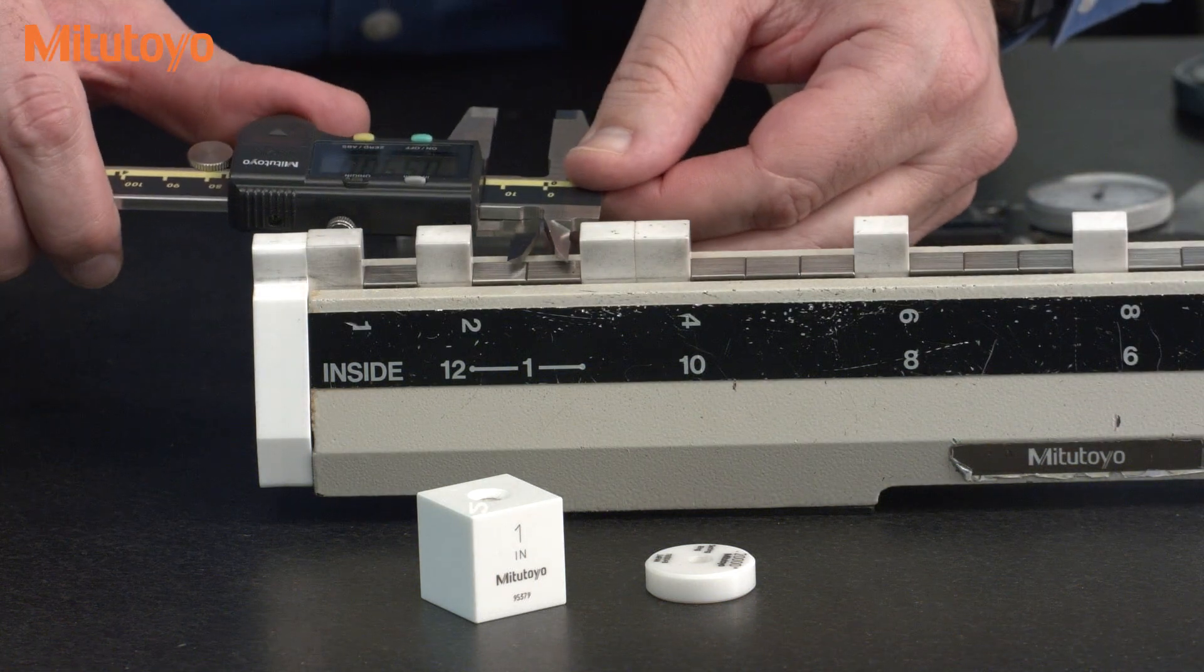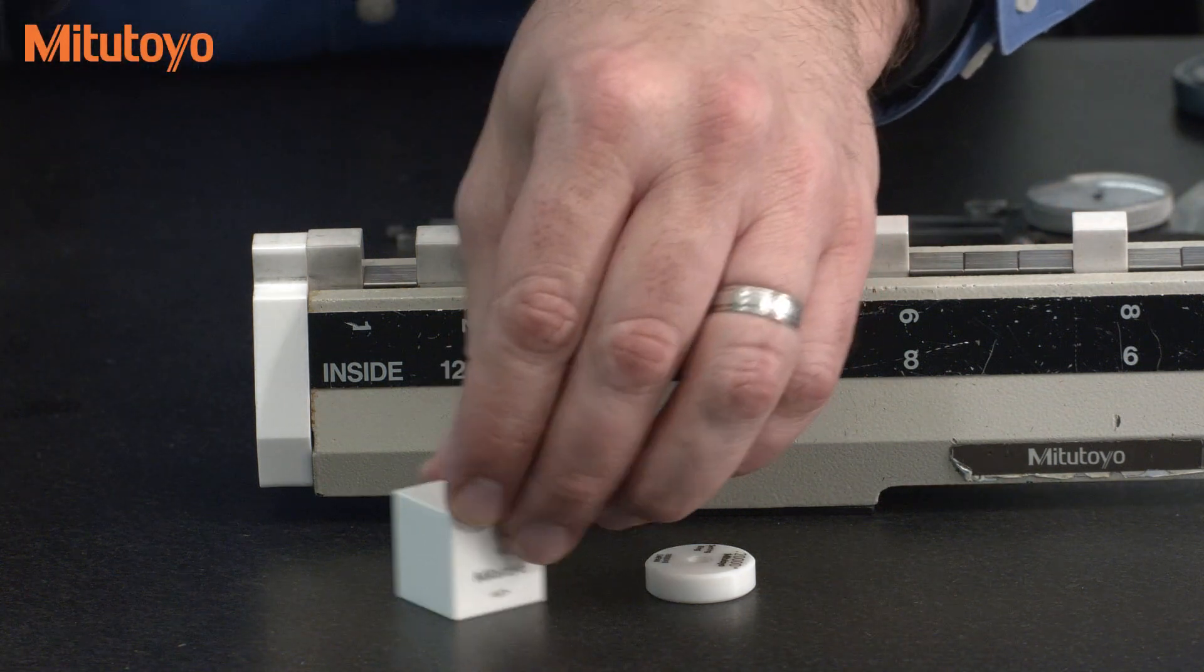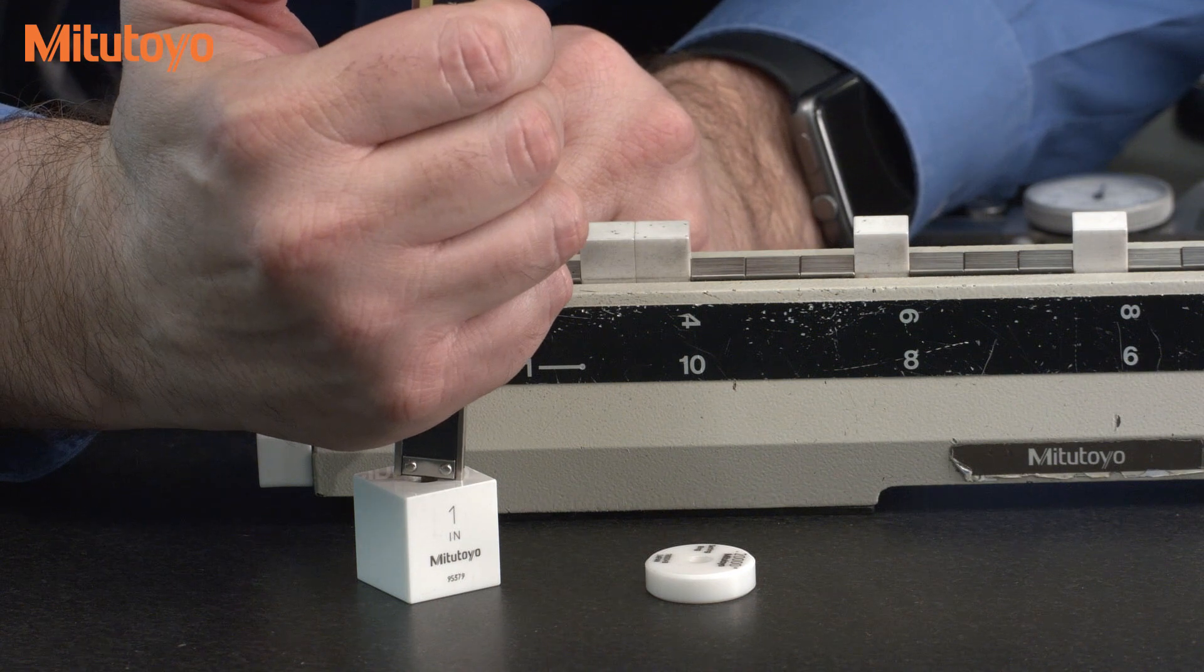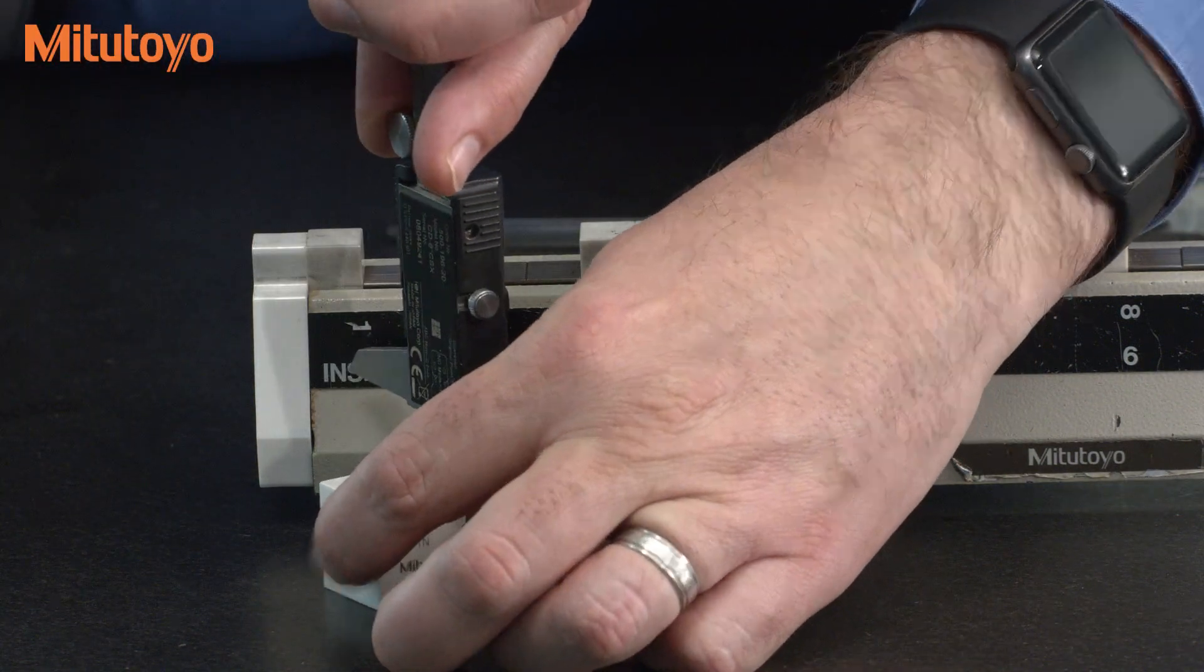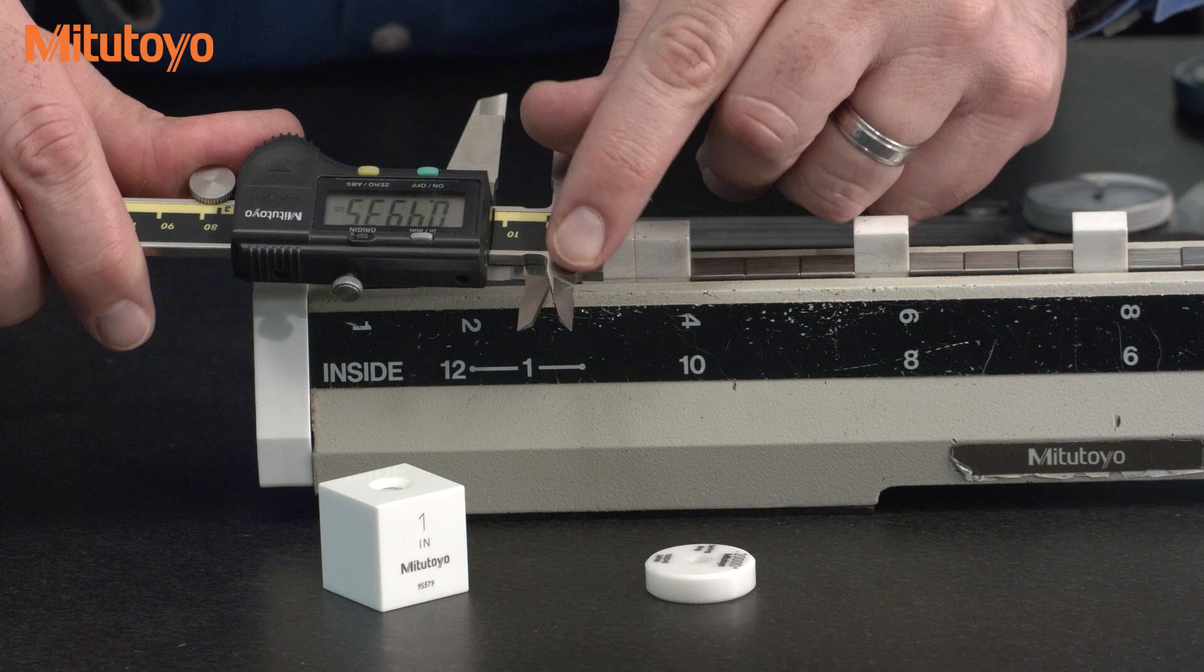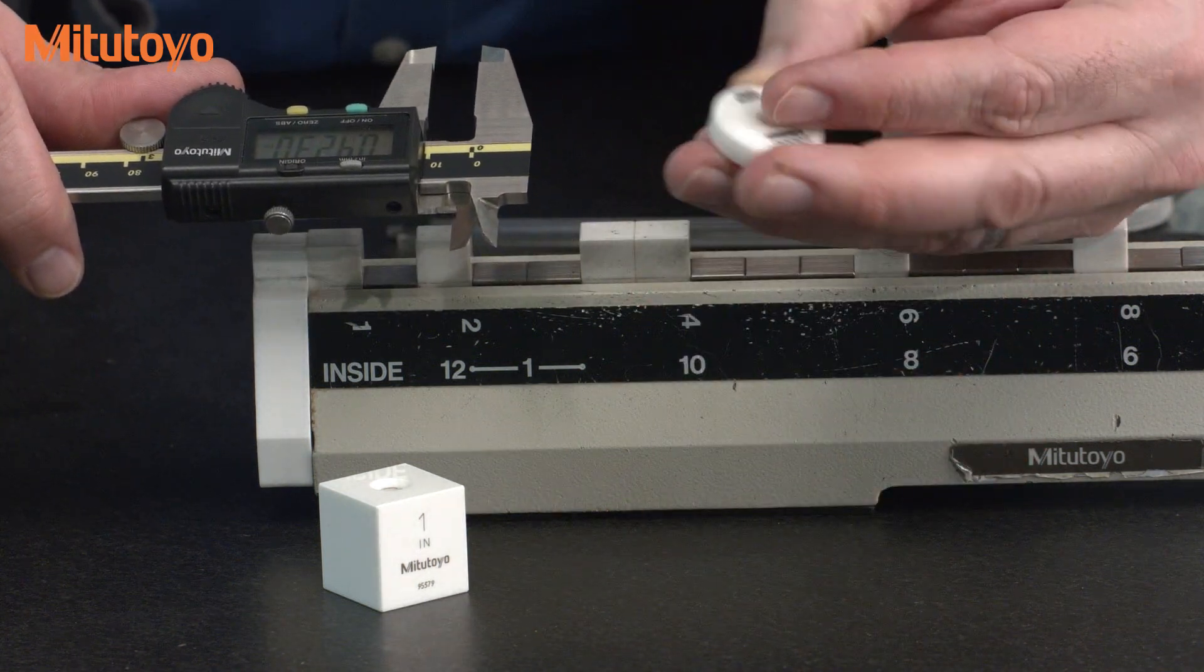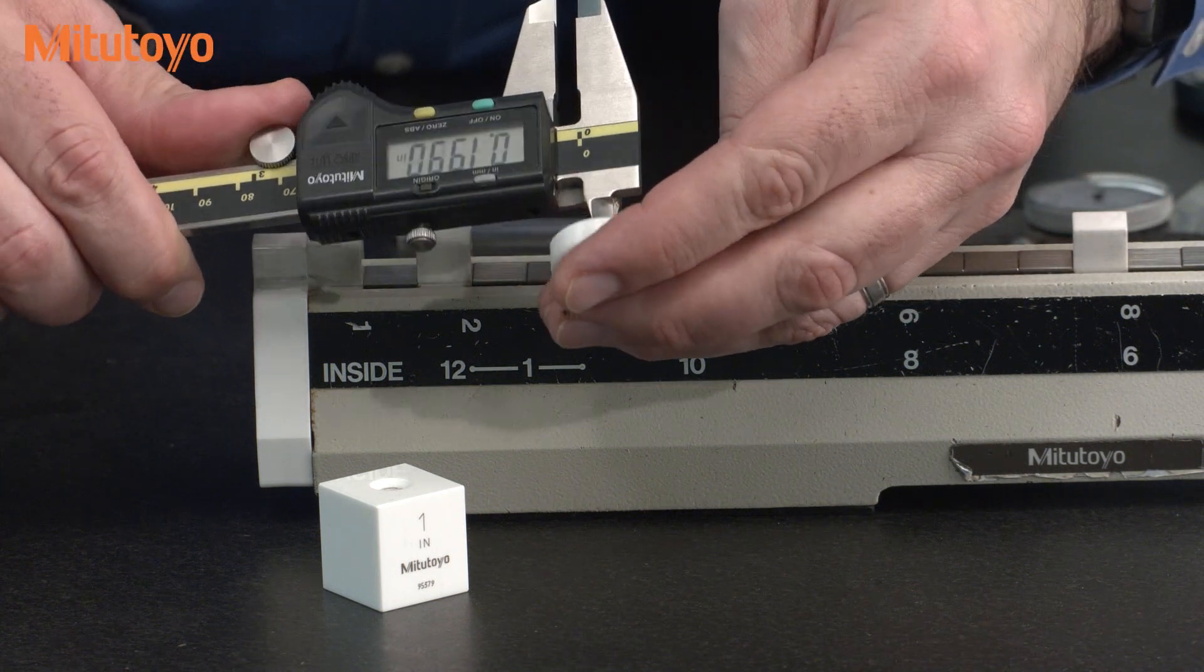Then we do an inside measurement, one inch like this. Then for the depth bar, we do a measurement like that. This caliper has a step function, so we do a measurement like that. And then to make sure that we don't have any problems with the small inside knife edges, we measure a two hundred thousandths ring gauge like that.